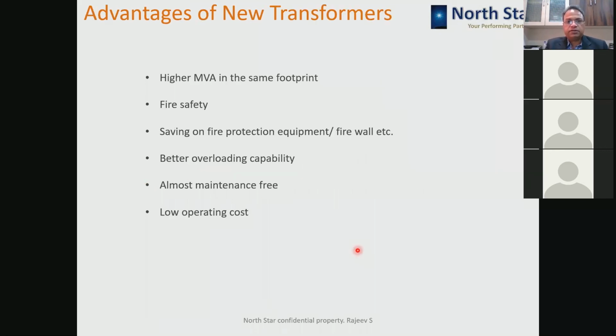Okay. Advantages of new transformers when you go for natural and synthetic esters. What is the advantage? You can go for the higher rating. You can increase the rating of the transformer without increasing the dimension of the transformer. So you can put the transformer in the same floor area as mineral oil, but with a higher capacity. Fire safety, you are improving, and you don't need fire protection equipment, firewall, etc. when you are using esters.